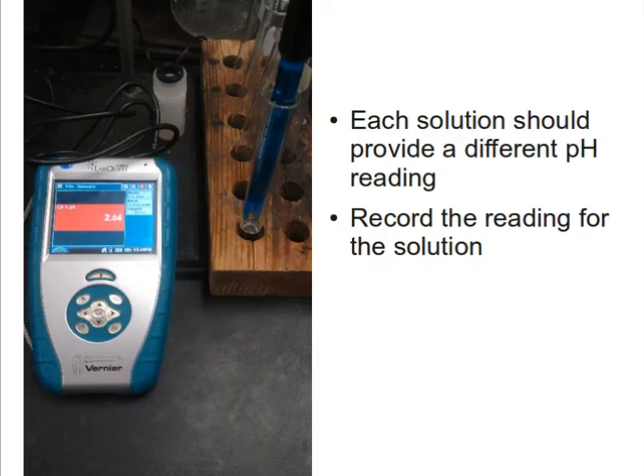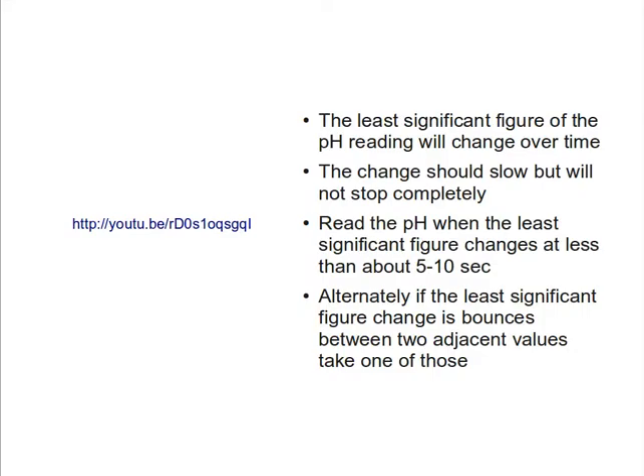Each different solution in this lab should provide a different pH reading. The pH reading will change when the probe is placed into each solution. The rate of this change will slow to nearly stopped, but will unlikely stop completely. When the least significant figure changes at a rate of every 5 to 10 seconds, record the value and move on. Alternately, if the least significant figure is bouncing between two values, record one of those and move on.